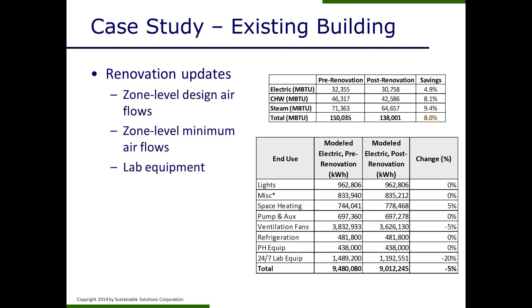And then on top of that, part of this project was to also look at some additional energy conservation measures that could be incorporated into the design while this renovation is occurring. So here's one thing we looked at, supply temperature reset. As the building is currently operated, the air handlers supply 55-degree air to the VAV boxes, which then reheat the air as necessary to meet the temperature set points. We found that by implementing a supply temperature reset, which is now actually required by code for a lot of systems in some climate zones, there'd be over a 20% savings in chilled water usage.